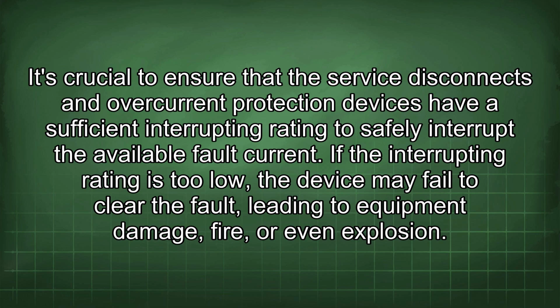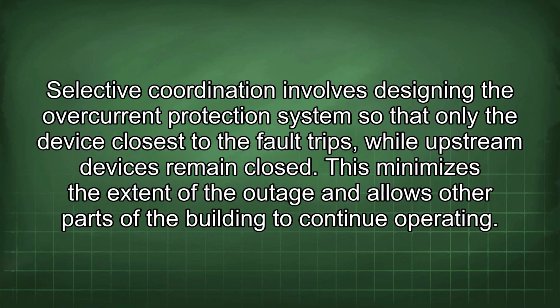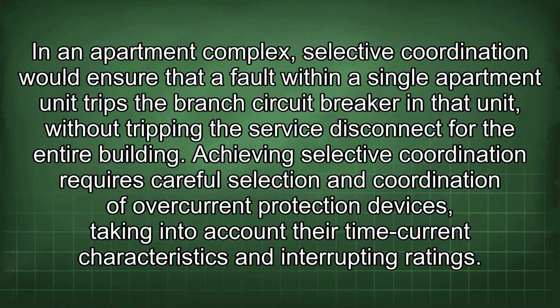or even explosion. Selective coordination involves designing the overcurrent protection system so that only the device closest to the fault trips, while upstream devices remain closed. This minimizes the extent of the outage and allows other parts of the building to continue operating. In an apartment complex, selective coordination would ensure that a fault within a single apartment unit trips the branch circuit breaker in that unit, without tripping the service disconnect for the entire building.